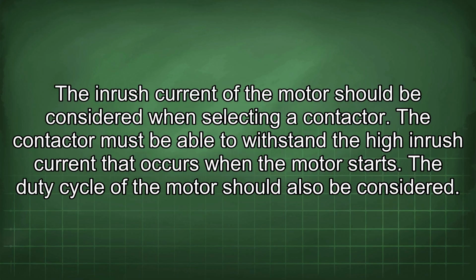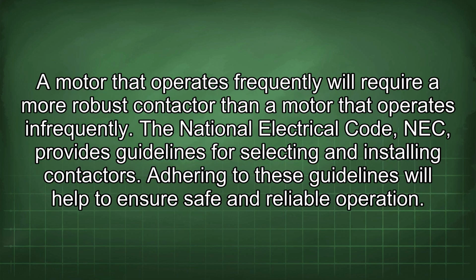The inrush current of the motor should be considered when selecting a contactor. The contactor must be able to withstand the high inrush current that occurs when the motor starts. The duty cycle of the motor should also be considered. A motor that operates frequently will require a more robust contactor than a motor that operates infrequently. The National Electrical Code, NEC, provides guidelines for selecting and installing contactors. Adhering to these guidelines will help to ensure safe and reliable operation.